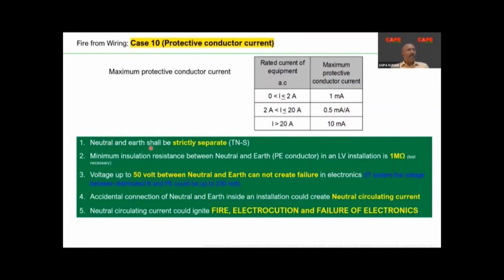So neutral and earth inside your building must be strictly separated. Never connect neutral and earth wire together. Both must be strictly separate. The minimum insulation resistance between these two must be 1 mega ohm. You must test it. A voltage of up to 50 volt between neutral and earth is absolutely no problem for your electronics and no problem for fire. This cannot create a shock or a hazard. I'm talking about the voltage between neutral and the earth. Remember, in hospital, an unearthed system called the IT system is recommended, where the neutral to earth voltage can even go to 230 volt. Accidental connection of neutral and earth inside an installation could create neutral circulating current. Neutral circulating current means the current which is supposed to go through the neutral will go through the earth wire, which will create fire, electrocution, and failure of electronics.